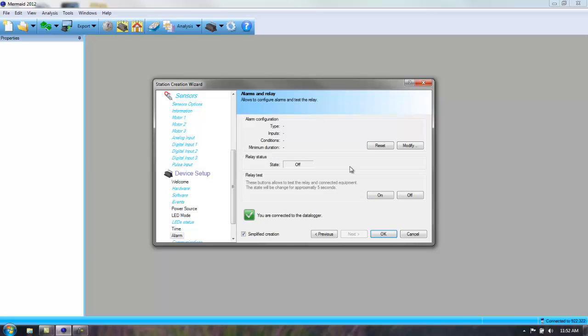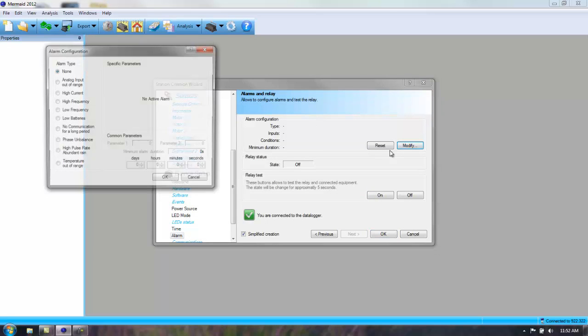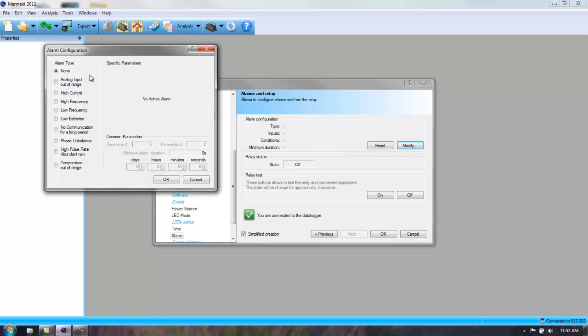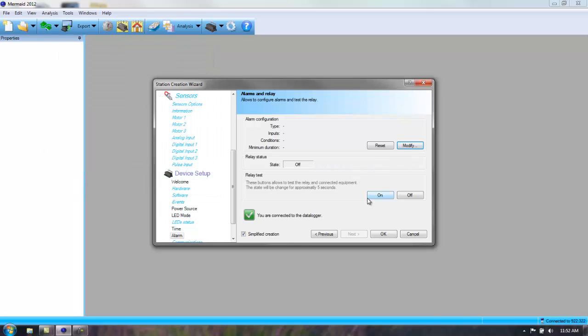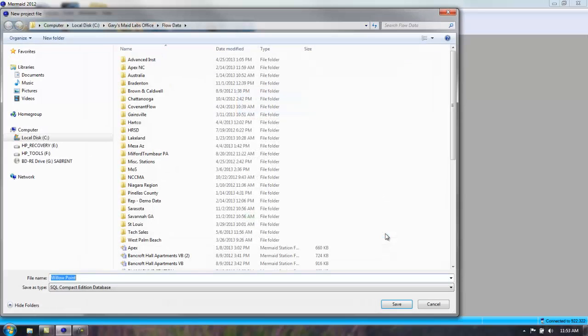Now for the alarms and relays, you can modify how you want to output your digital output. You can have no alarms, or you can select high temperature, high rain event, phase imbalance, and there's a few more, like low batteries. You can have a digital event, and this could go to your SCADA system if you wanted to as a digital input. And also you can check your relay by hitting on and off, and you can physically hear it clicking inside the data logger. At this point in time, just hit OK.